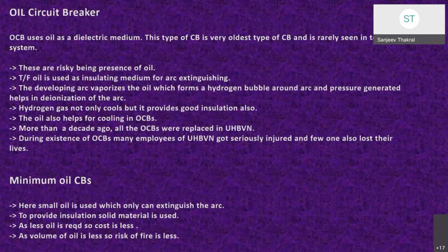Here the contacts open inside the oil. The developing arc vaporizes the oil, which forms a hydrogen bubble around it, and the pressure generated contributes to the deionization of the arc. Hydrogen gas not only cools, but it also provides good insulation. Oil also helps in cooling the OCBs.